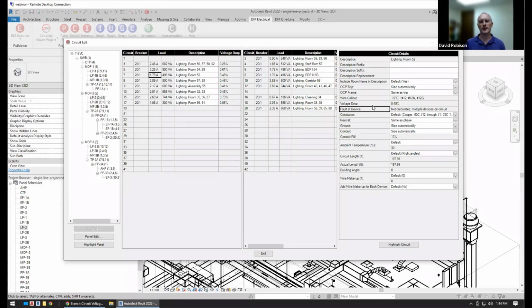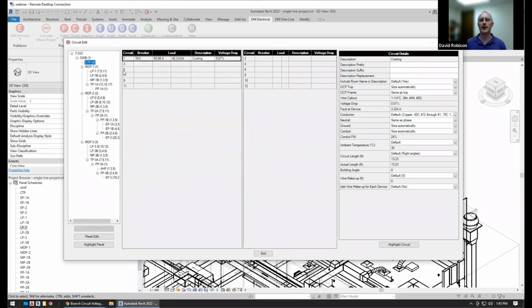If it's two or three, we kind of average the distance, because sometimes you'll circuit up the disconnect separate from a piece of equipment. So you'll have two devices, but it's really only one. So you still want the fault. It's really intended for a single piece of equipment on a circuit. So again, if we go back to our CTP where we have our cooling tower, here's the fault at that cooling tower, which is something that you might be interested in.